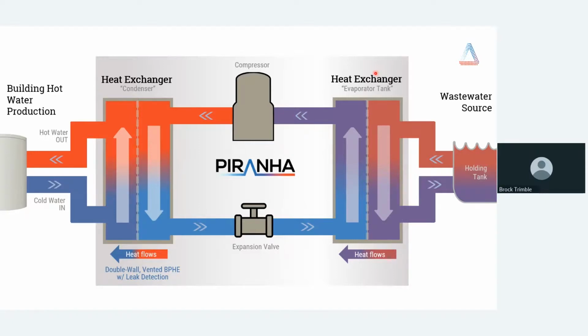So what we've done is to develop what we call our evaporator tank. With this, we pump wastewater, all of that raw, black, untreated wastewater, into that evaporator tank. We make sure that we're separating everything, keeping the wastewater on one side, and then we have the refrigerant on the other. The refrigerant absorbs the energy from that wastewater, runs it through a compressor, and outputs a much higher temperature in the refrigerant. And all of that really hot energy is then transferred into your water, your potable water, across the wall of that very specialized potable condenser, delivering hot water into your building on an ongoing basis.